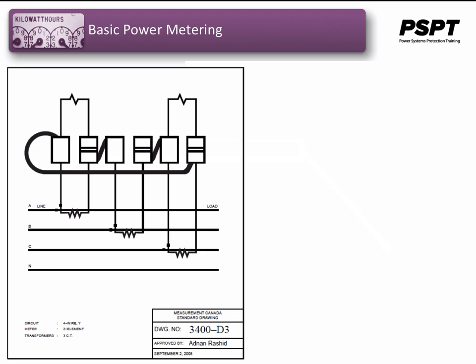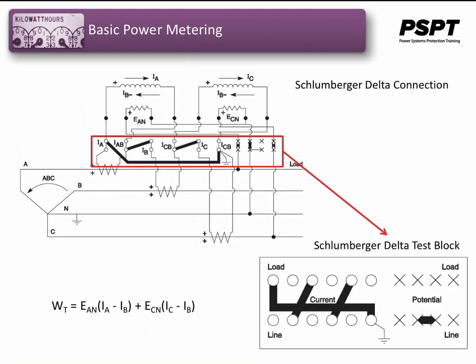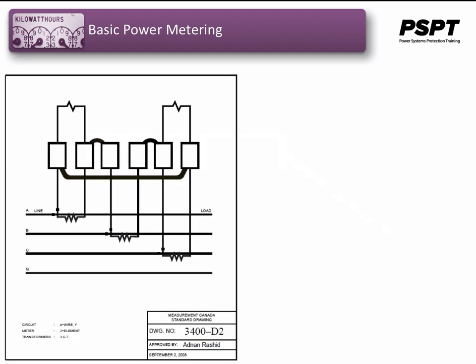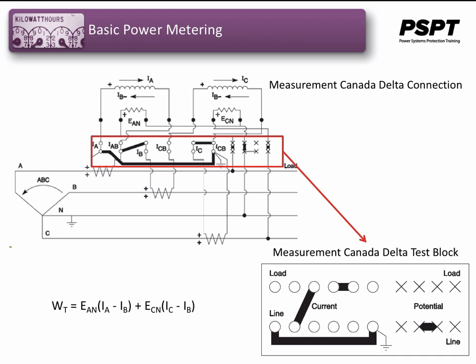This figure shows a typical installation of a 2-element meter with a Schlumberger delta connection. And this figure shows a typical installation of a 2-element meter with a Measurement Canada delta connection. Now these connections basically read the same to the meter, or the meter reads the same current. It's just that the wiring on the test switches themselves are different.